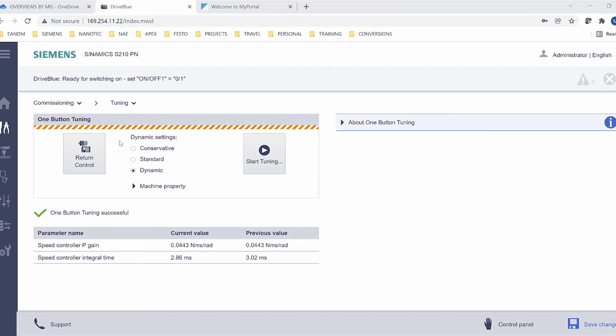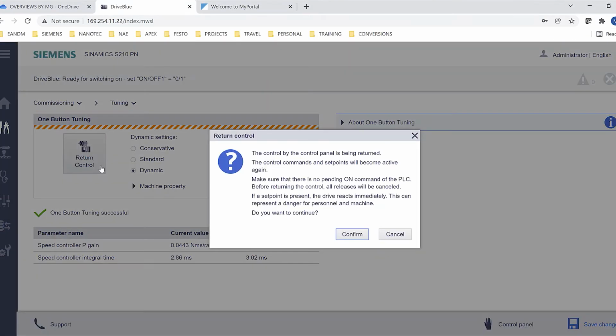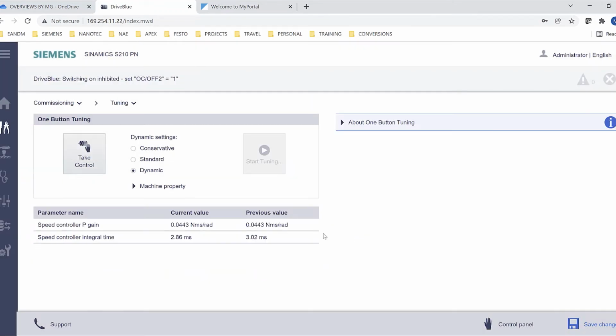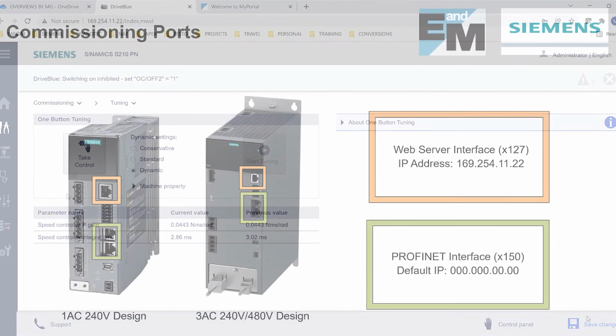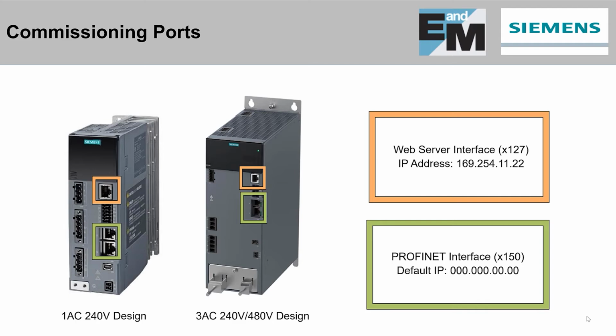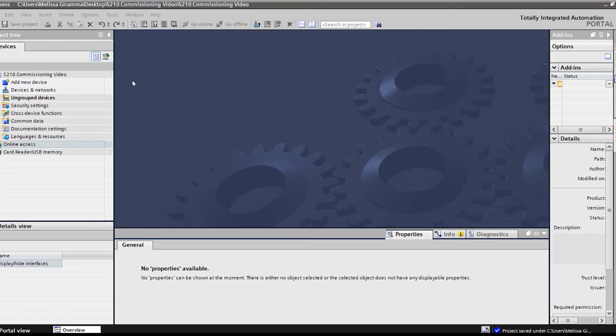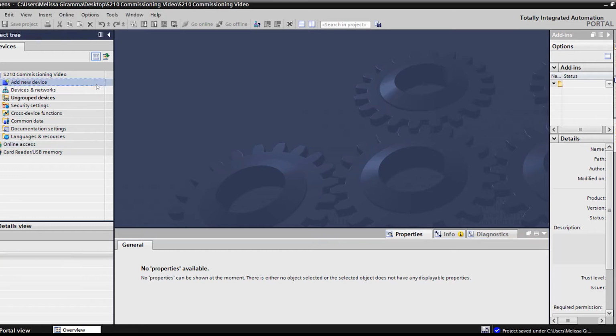Once complete, a green check mark will appear letting you know that the tune was successful. Then you can click on Return Control and select Confirm. This completes the minimum commissioning steps for the S210 using the web server. We can select Save Changes. Now, let's take a look at an S210 setup using the Profinet port and Start Drive in TIA Portal.